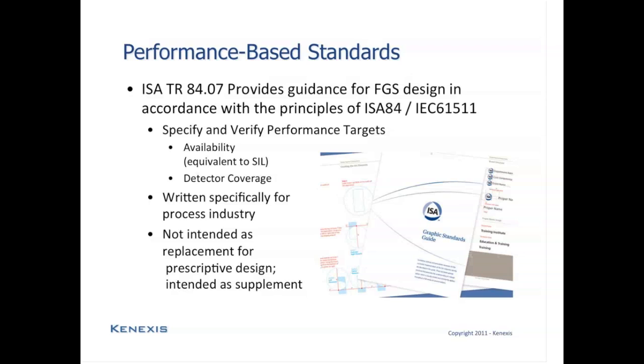Now, this standard was specifically written for the process industries and was not intended to be all-encompassing, going back to your typical occupied buildings. So again, we're only going to be looking at the process areas of a facility when we start using the technical report as a basis for the fire and gas system design.